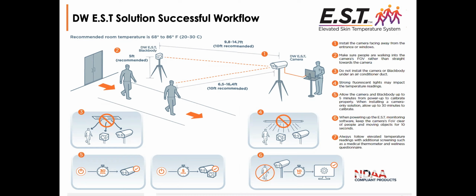Number 5, when you set up the camera itself - this is something I hadn't mentioned - it is a quick setup, but once you've set it up, you want to do a bake-in. Without a black body device, you're going to need 30 minutes before you want that system to be operational, to let the camera acclimate to a location. Using the black body and the camera together, it can be just 5 minutes.